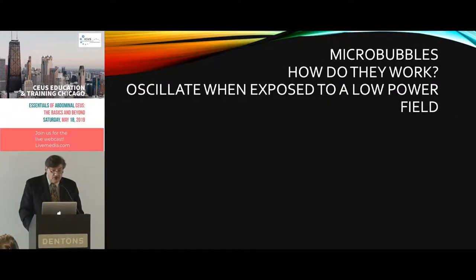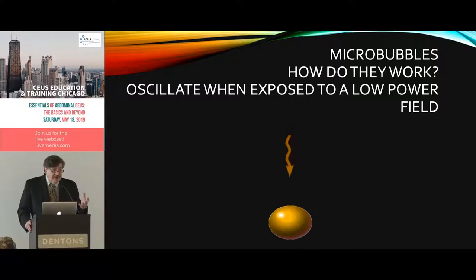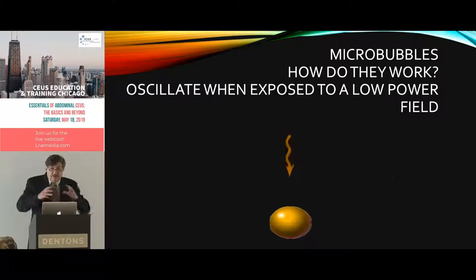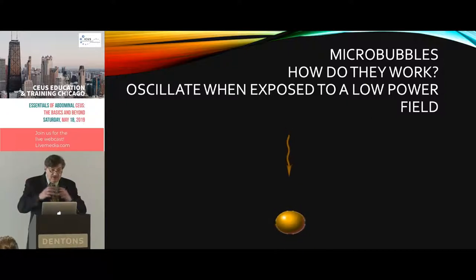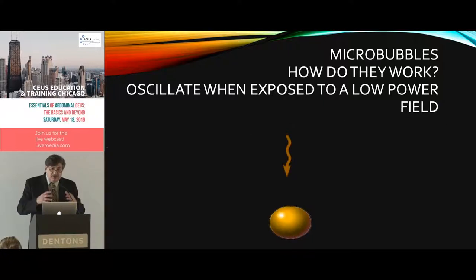These bubbles oscillate when we resonate them. At very low power levels we get a linear response — they expand and contract about the same. As we increase power, the bubbles can expand more than they can shrink, giving us a nonlinear response. If we increase the mechanical index even further, we make them expand so much that they actually explode. So we have three different MI levels: linear response, the low-MI nonlinear response we use for imaging, and high MI which just destroys the bubbles.